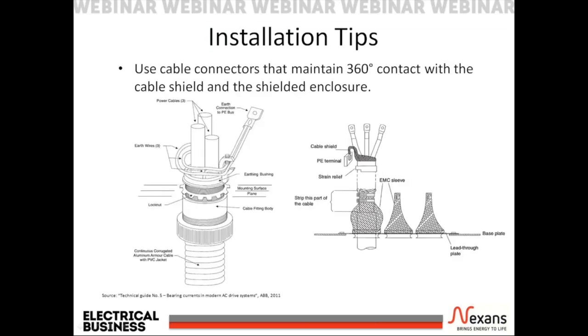When terminating the cable shield, which is also a current path, it's important to electrically connect it to the protective earth terminal or ground at both the VFD and the motor. Choosing a cable connector that maintains 360-degree contact with the cable shield and the shielded enclosure is critical.